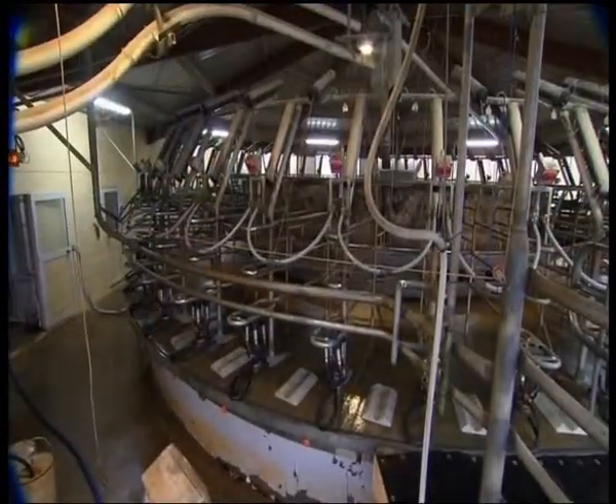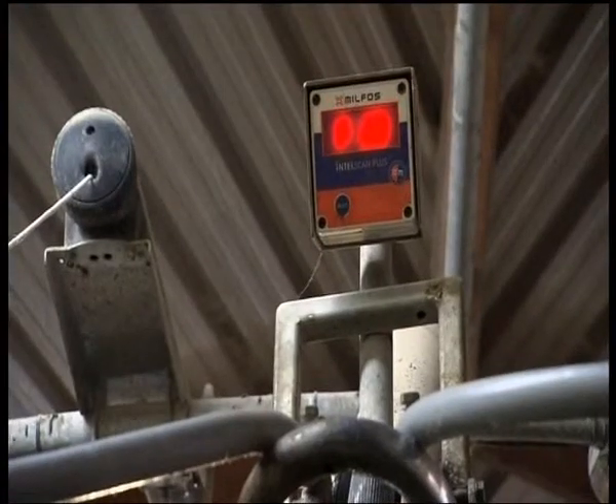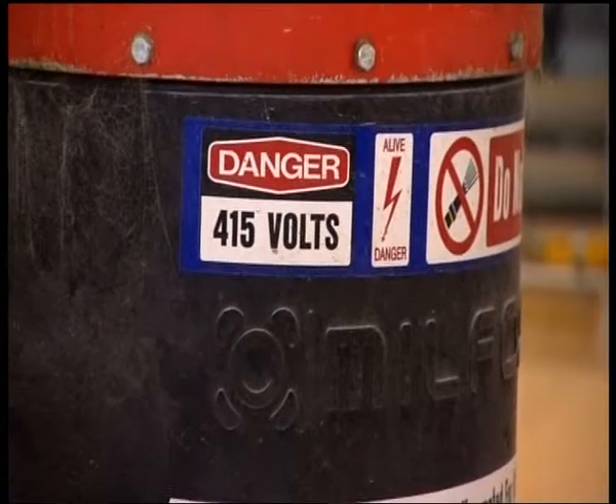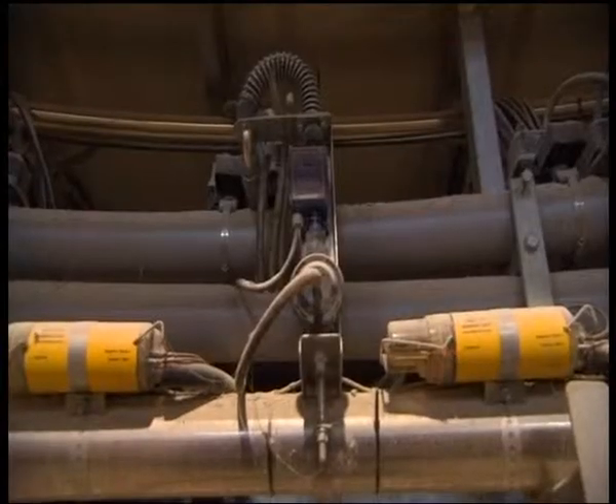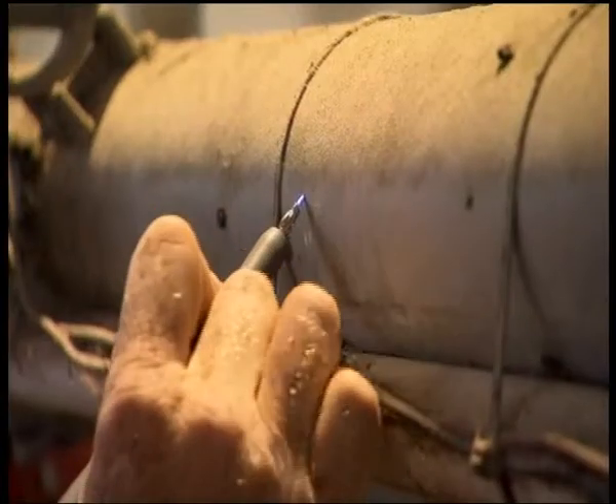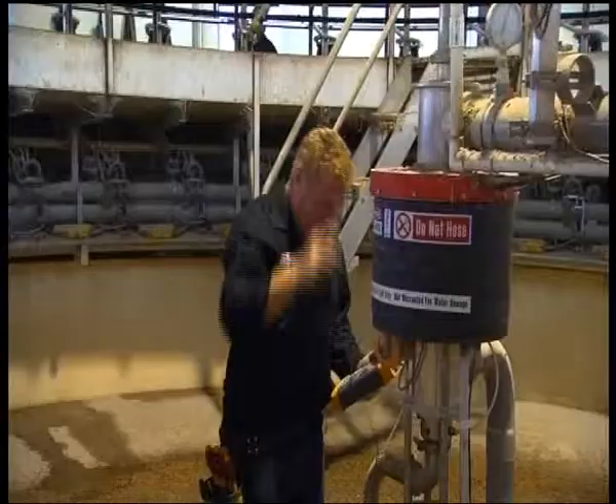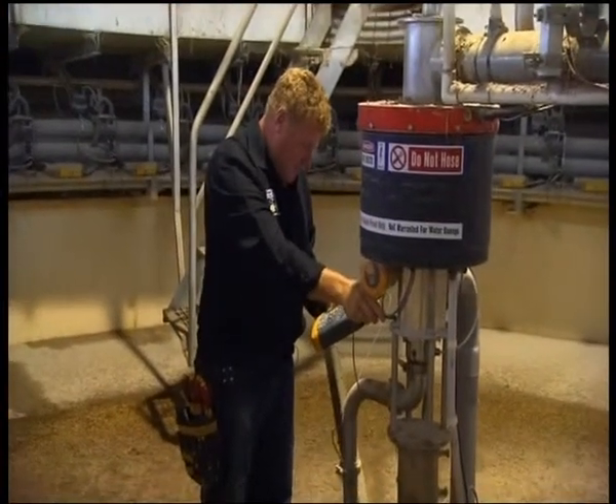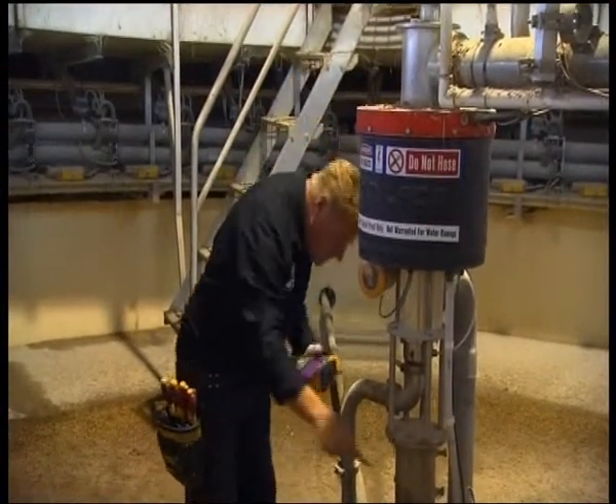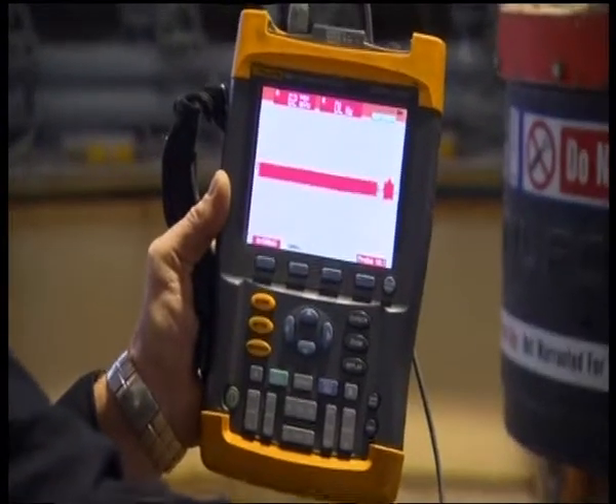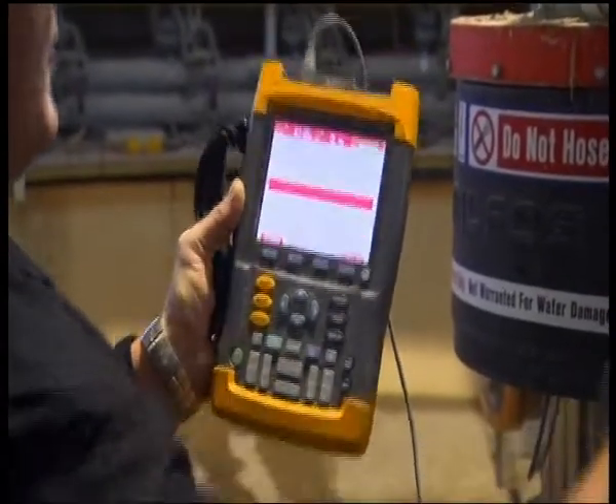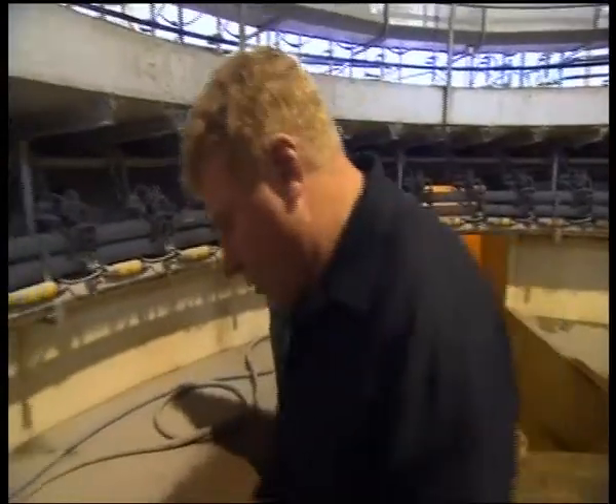The modern dairies, more and more, they've got good power supplies, they're bigger, they have their own transformers. It's taken away the neutral effect type stray voltages. And now we have this harmonic stray voltage as it comes from switch mode power supplies and variable speed drives. And this is a totally different type of stray voltage. So stray voltage is a very broad term. Righto, Grant, I'll show you what I've found wrong.